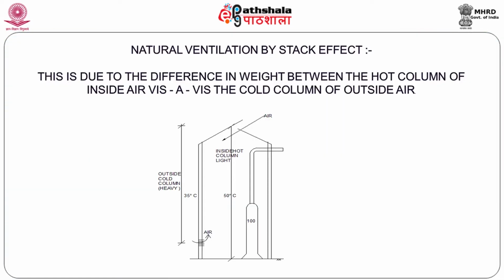The other factor which affects natural ventilation is stack effect. Now this generally happens in industrial climates. For instance, on the slide you see a boiler. Its shed is generally a big shed, a tall shed. Now the moment you have a tall shed, the general tendency is to put louvers all over, that means louvers from the floor up to the ceiling. Such louvers will depend entirely on wind effect.